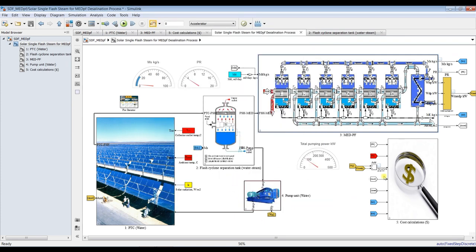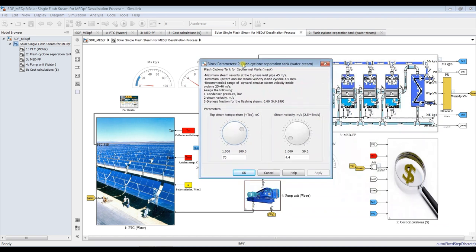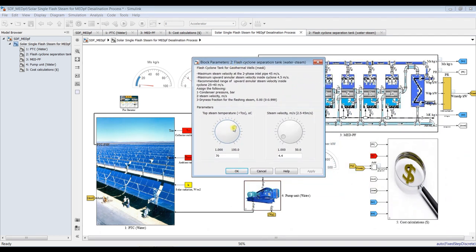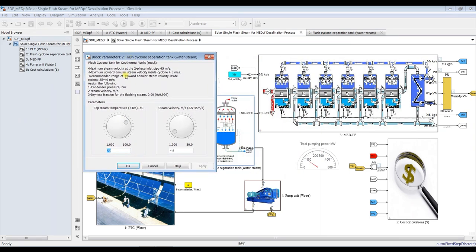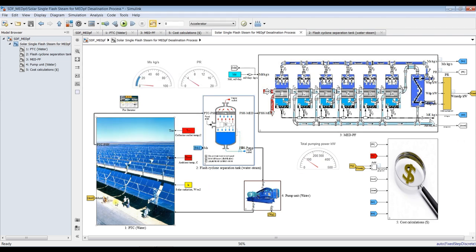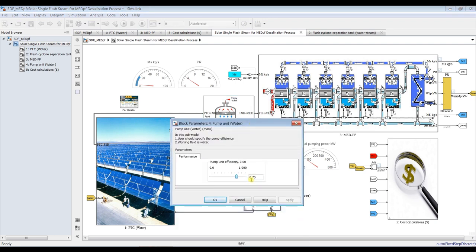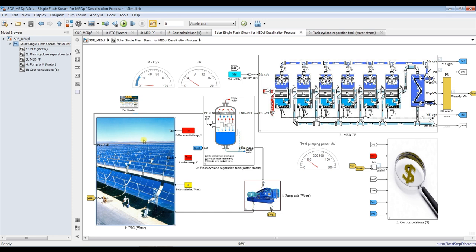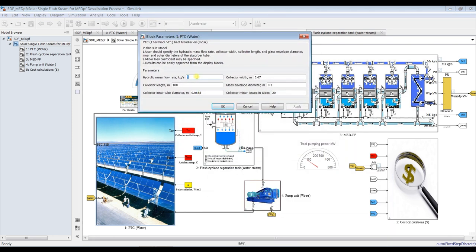For the flash evaporation tank — this is very important. Don't forget that we assigned our hot water temperature at 160 degrees Celsius. Therefore, the top steam temperature suitable for the first effect is normally 65 or 70 degrees. This is the steam velocity — I will keep this value. For pumping, we are keeping our efficiency at 75. For the parabolic trough collector, I will keep the design values as they were.